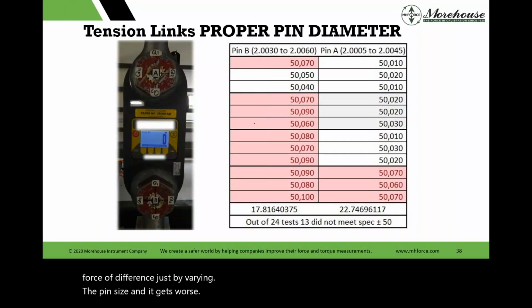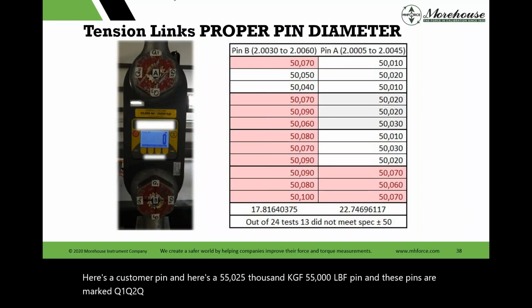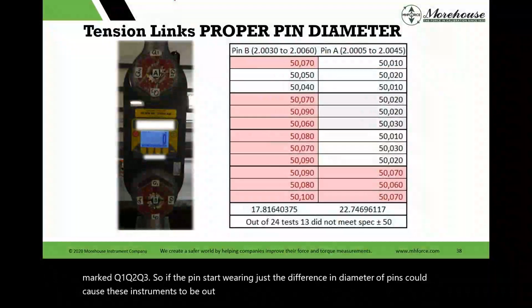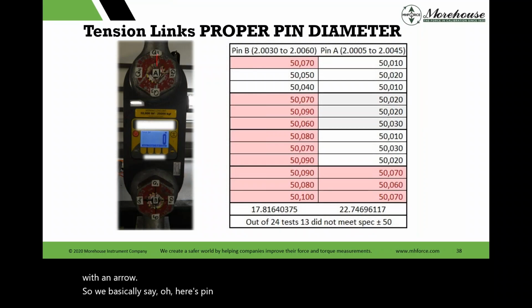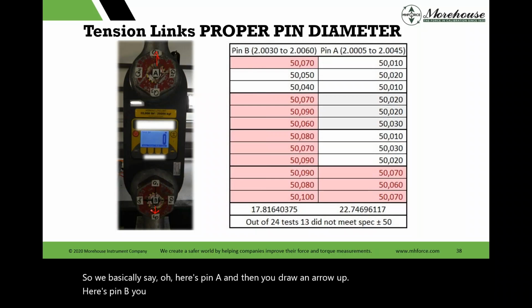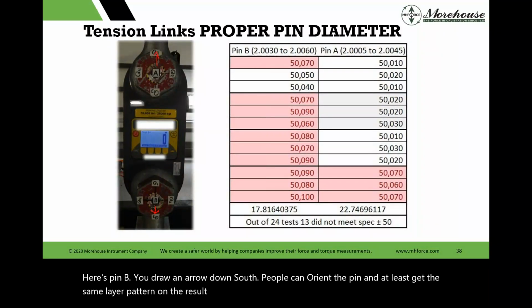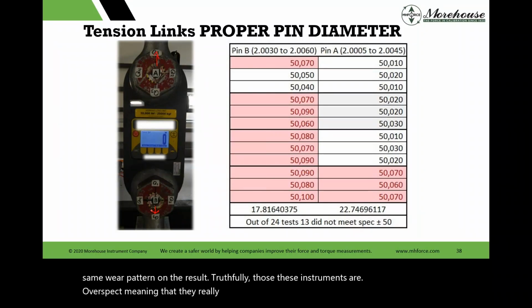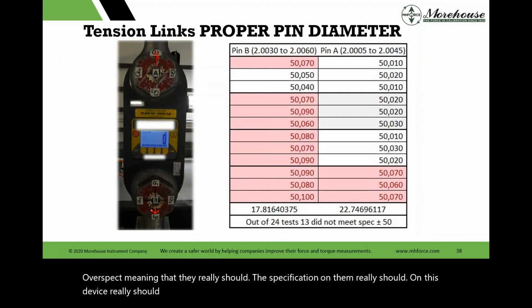Here's a customer pin, and here's a 55,000 LBF, 25,000 KGF pin. And these pins are marked Q1, Q2, Q3. So if the pins start wearing, just the difference in diameter of pins can cause these instruments to be out of tolerance. So we got into a habit of marking the pin top with an arrow. We basically say, here's pin A, and you draw an arrow up. Here's pin B, you draw an arrow down. So people can orient the pin and at least get the same wear pattern on the result. Truthfully, these instruments are overspec'd, meaning that the specification on this device really should be plus or minus 100 pounds and not plus or minus 50. They should be a 0.2% device.